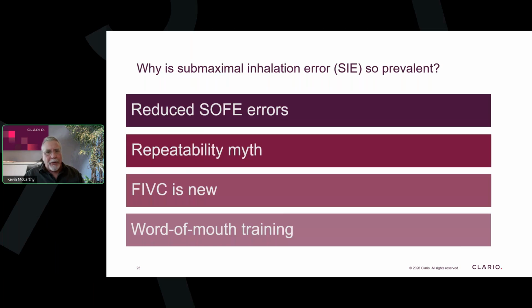So if people were just evaluating their own technique, for example, or they're participating in clinical trials and getting feedback from overread, they would see, oh yeah, I'm doing a great job. I'm getting acceptable FVCs and FEV1s. The data is repeatable. End of story. I'm good. But you add the FIVC to the mix. You add the evaluation of full inflation, and sometimes you're revealing that that data is not something you want in the clinical trial, that it didn't start from full inflation.